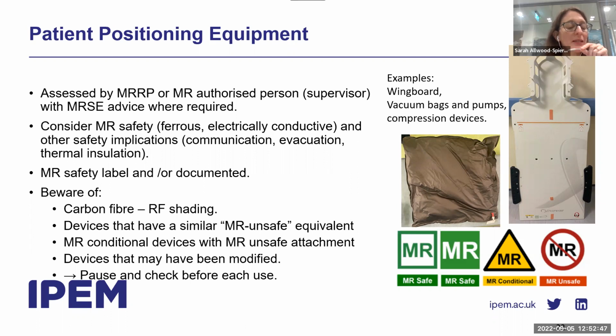Does it thermally insulate the patient and mean that they might heat up during the scan? Once this has been assessed, it can have an MR safety label, either safe or conditional, and it must be documented, with documentation on the conditions and where it's kept within the department. It's really important that if something is to be used in MRI only, it's kept within the MRI department, and beware of anything that maybe has a similar MR unsafe equivalent elsewhere in the radiotherapy department. Make sure that you have the right device in your department.